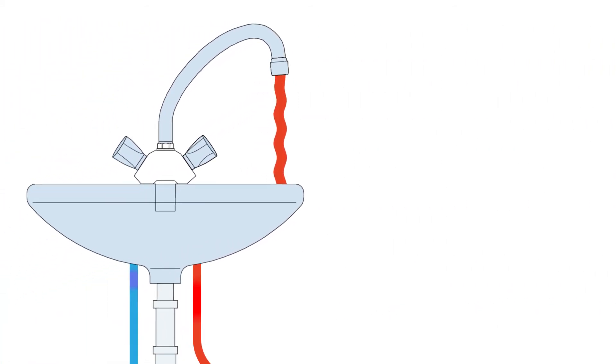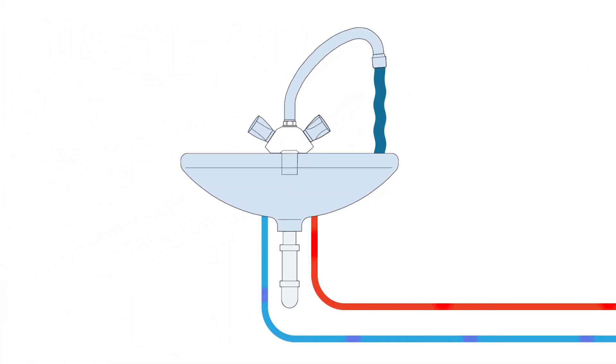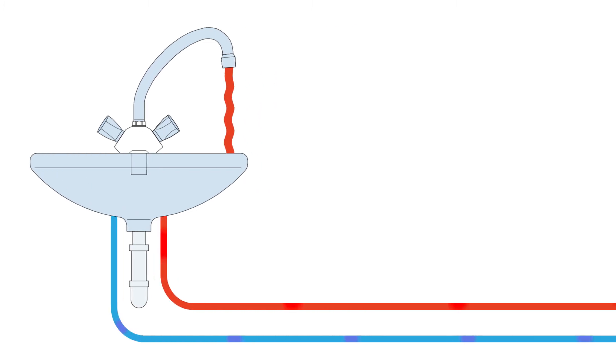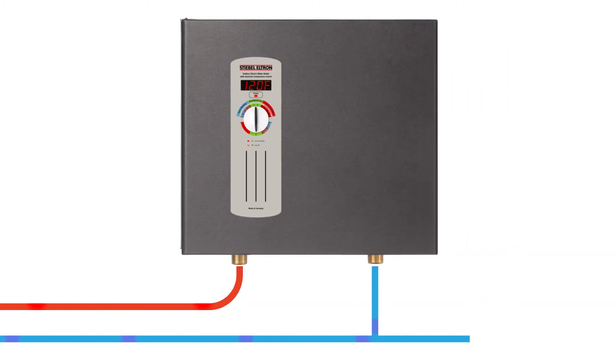This is true for every tankless water heater. If the demand exceeds the capacity of the unit, then either the flow rate or the temperature rise will be reduced. This is one of the most important considerations when purchasing a tankless water heater.